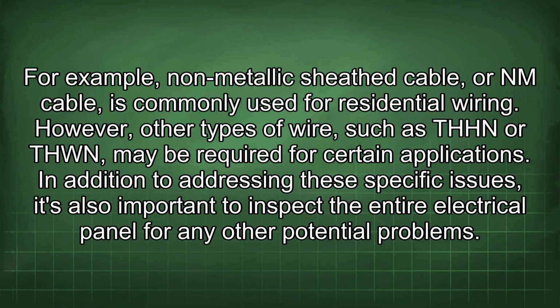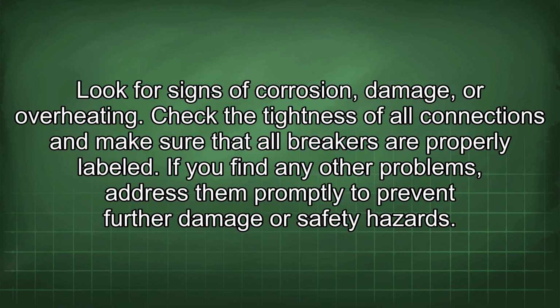In addition to addressing these specific issues, it's also important to inspect the entire electrical panel for any other potential problems. Look for signs of corrosion, damage, or overheating. Check the tightness of all connections and make sure that all breakers are properly labeled. If you find any other problems, address them promptly to prevent further damage or safety hazards.